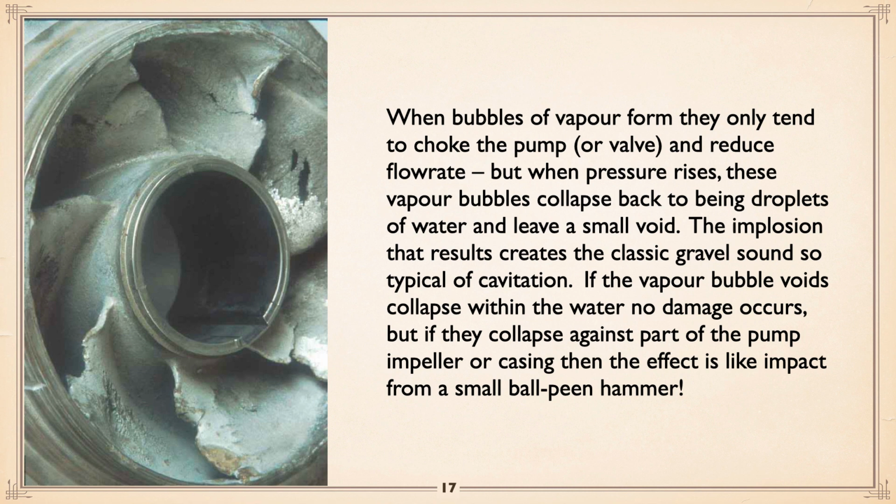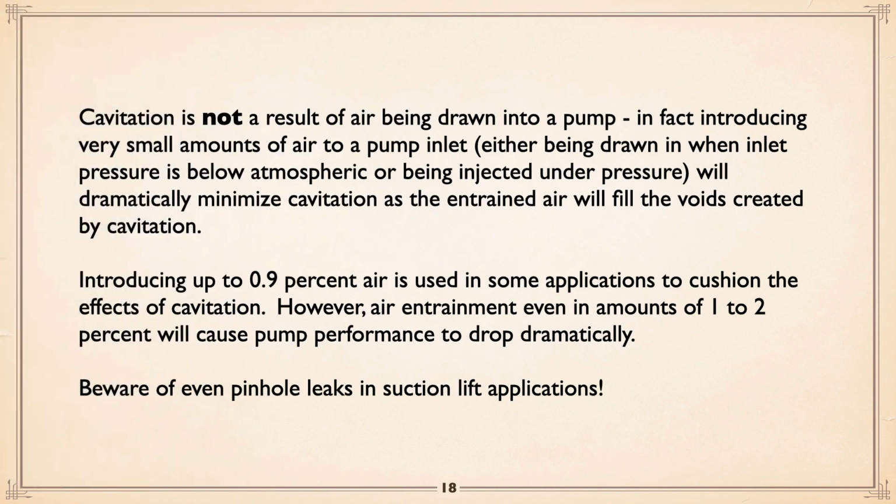Anyway, when that happens, it will attack the metal, and you can see, with some pumps in a matter of hours, most pumps, a matter of weeks. I've seen valves, 6 months, you'd look like somebody had gone at it and tried to cut it in half. So it's quite a dangerous little concern in terms of the life of the pump. As I say, it is not a result of air being drawn into the pump.